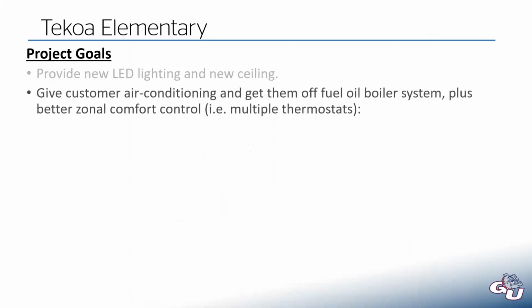Our goals on this project were to provide new LED lighting and a new ceiling. This customer really wanted air conditioning, and this boiler they had was run off of fuel oil. So they had a big storage tank underground that they would periodically have to fill. They'd call some shop down the road that would come fill their fuel oil storage tank. So this is a case where they didn't have natural gas. We've been talking about natural gas being the primary fuel for heating a building, but the rural areas a lot of times don't have natural gas at all. So their options are either to go with an electric heating system, which is expensive generally, or with fuel oil or maybe propane to heat their building.